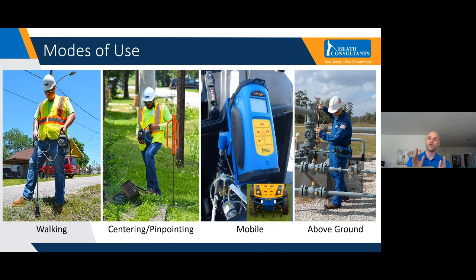So it can be used for centering, and then pinpointing, which is telling us where the actual leak is, or the highest concentration of the gas. So we're looking for the spread of the gas and the high concentration of the gas. It's really a very versatile instrument where you can do the walking and also the below ground subsurface sampling. It can also be used for doing mobile surveys.